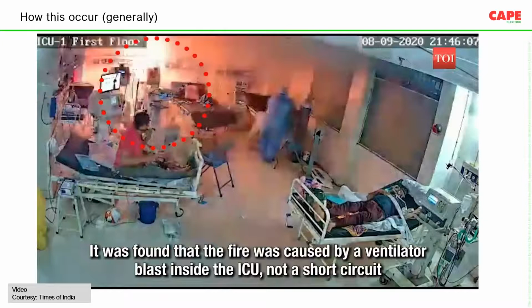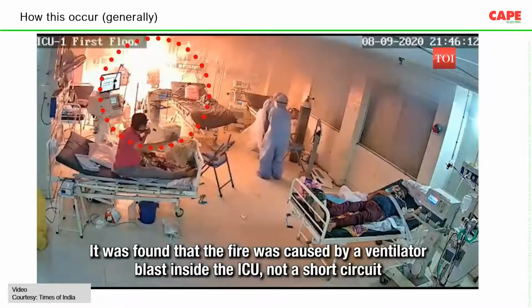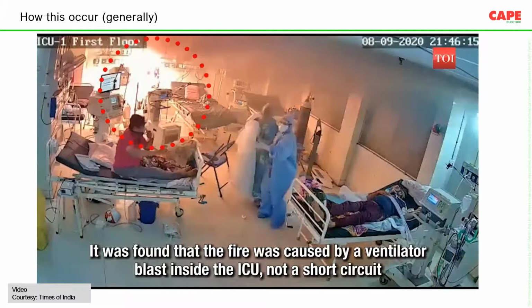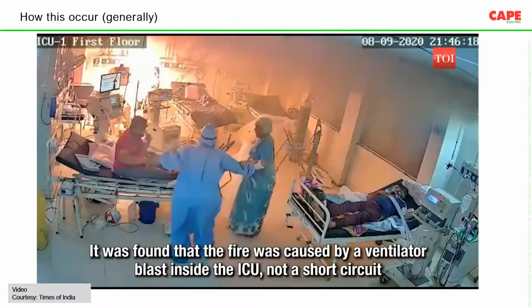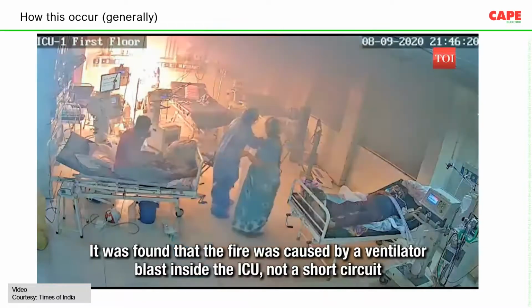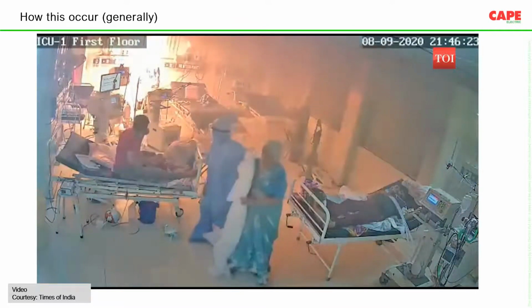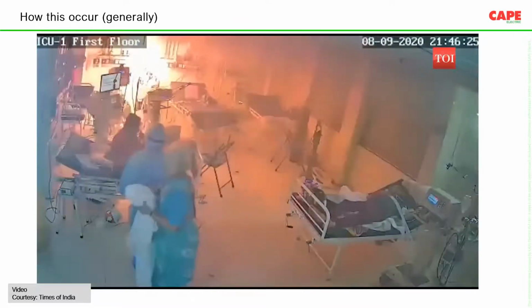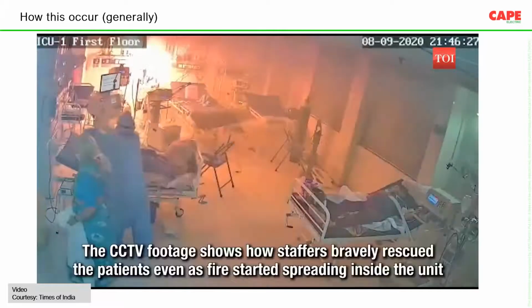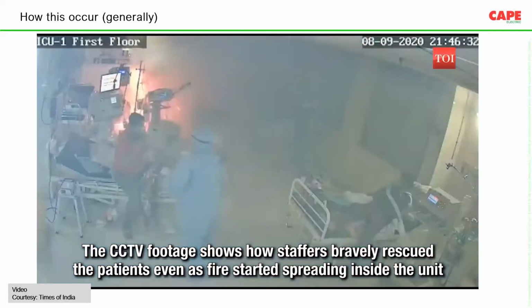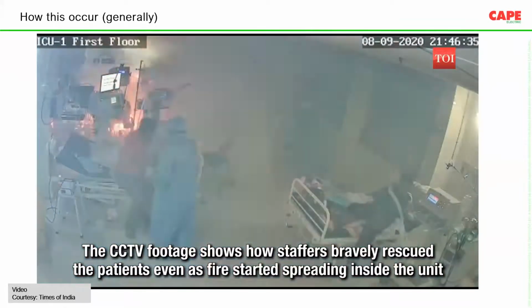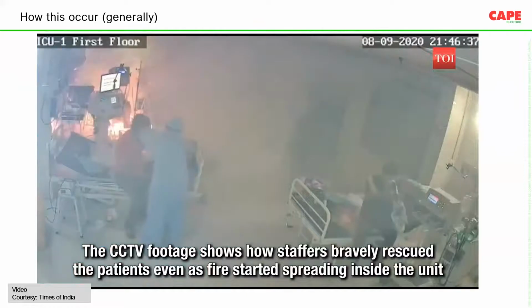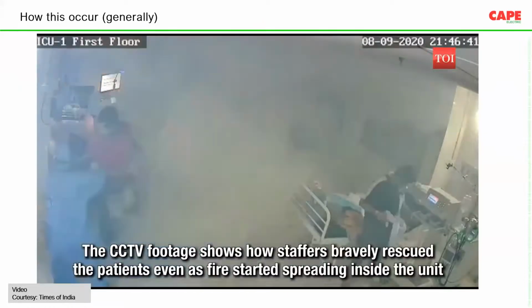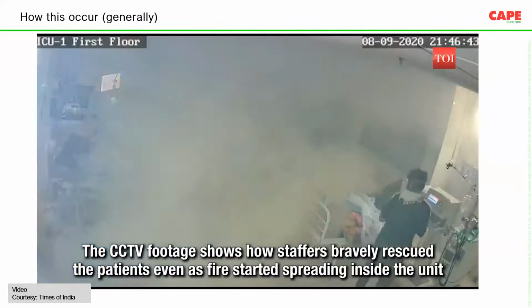You see how fast it is. So basically, that particular equipment started the fire. Electrical, we call it fire due to short circuit. This is how most of the time it happens. So fire starts from some electrical apparatus, and we must understand that the ignition of fire is not happening instantaneously. It takes a few seconds. Please understand, not minutes, a few seconds. And the seconds are probably 5 seconds, 10 seconds, 20 seconds.